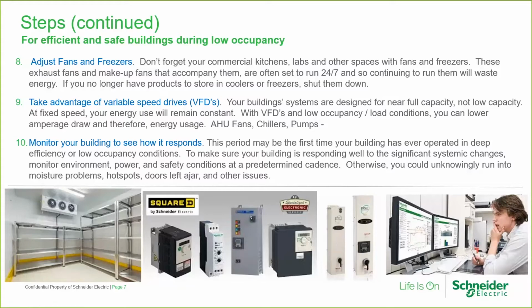Many people have variable frequency drives or adjustable frequency drives on pumps and air handling unit fans. These are perfect times to take advantage of those, reducing fan speed and airflow or water flow - although up north we have to keep water moving so pipes don't freeze. Engineers also want us to keep some airflow so you don't have stagnant areas, especially with these viruses around, but with no occupancy you can certainly reduce it. As before, we'll need to bring those back to normal speed when we return to normal occupancy.